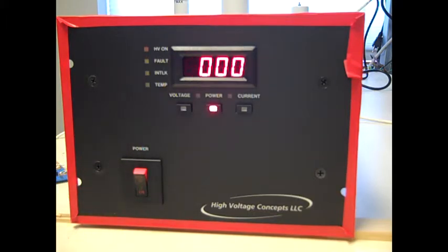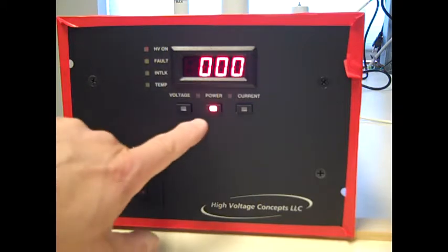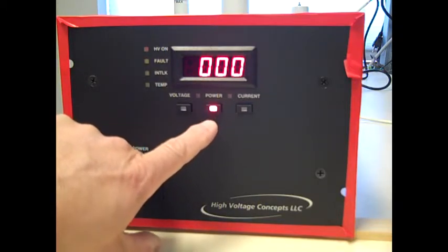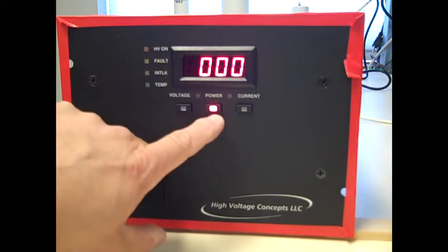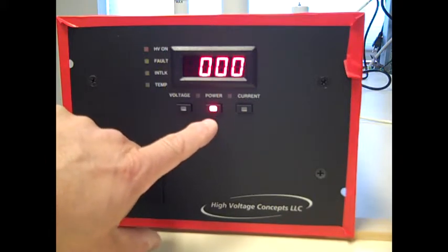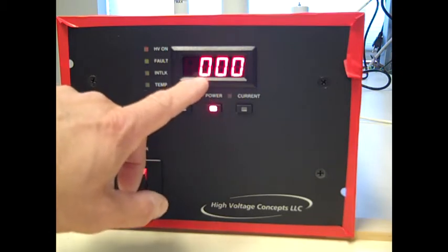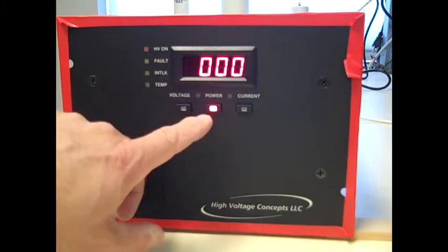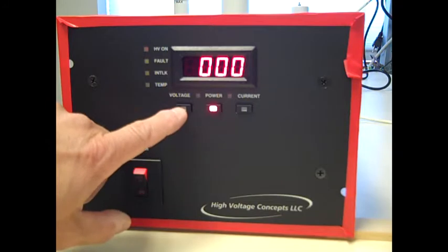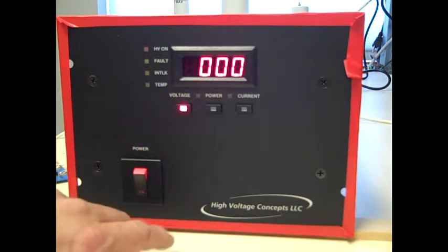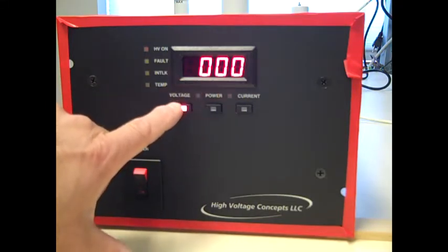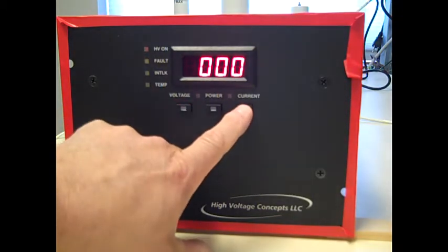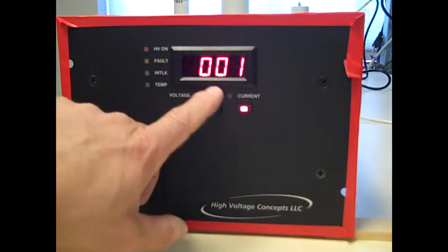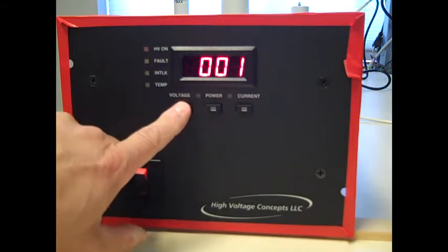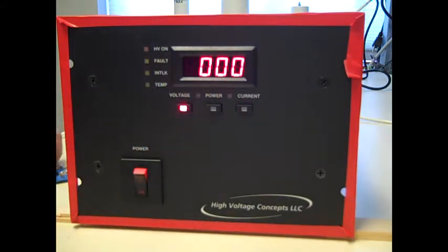Now when the power supply powers up, you'll see there's this LED lit here, and this is telling you that during power up the meter reads the power output of the power supply. If we depress this button, the meter will read voltage. If we depress this button, this tells you the meter is reading current. So let's start out in the voltage mode, and we'll go ahead and turn on high voltage on.